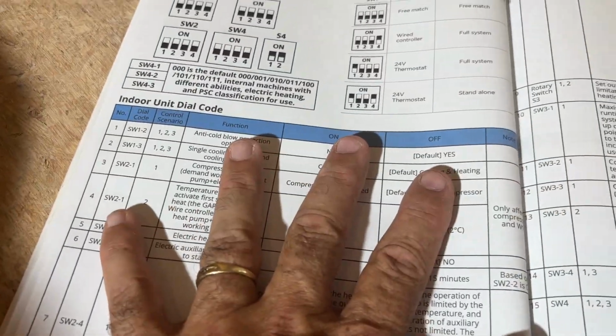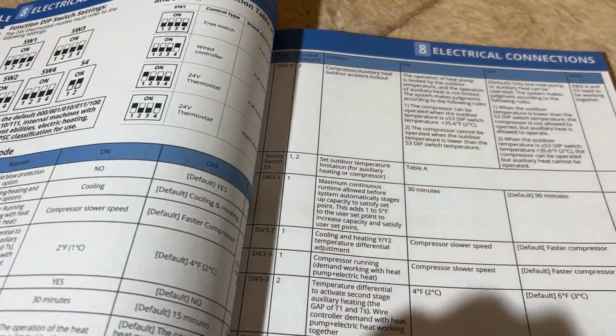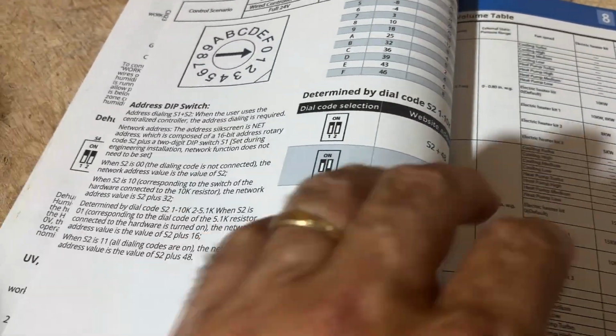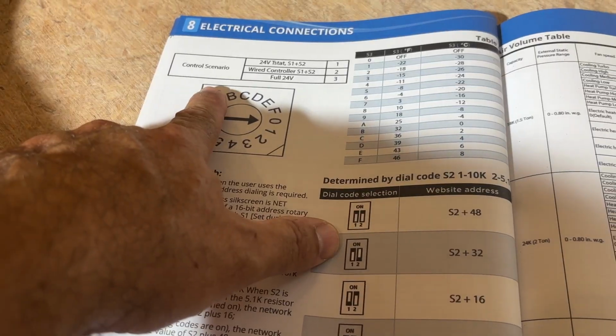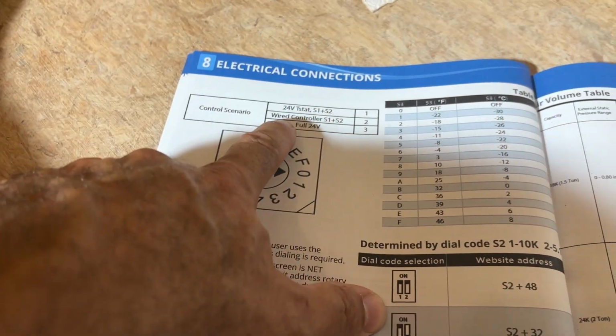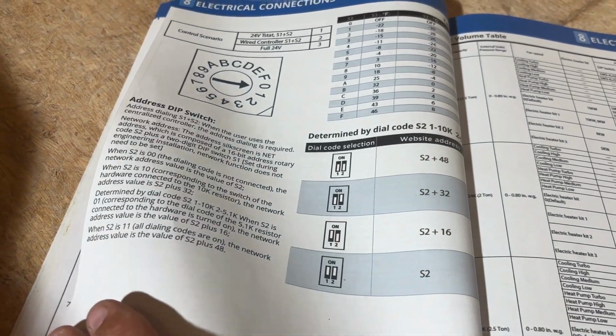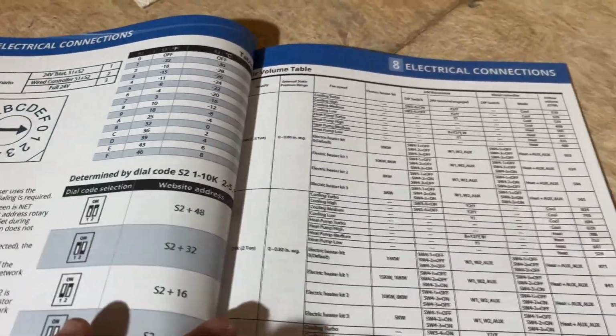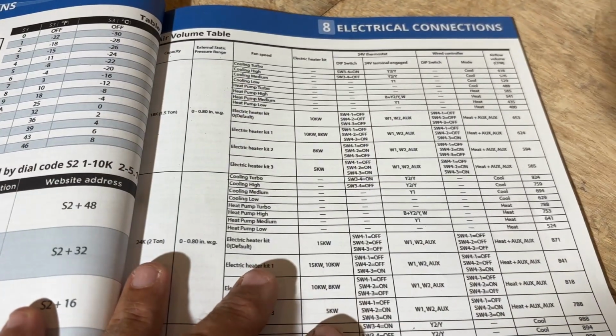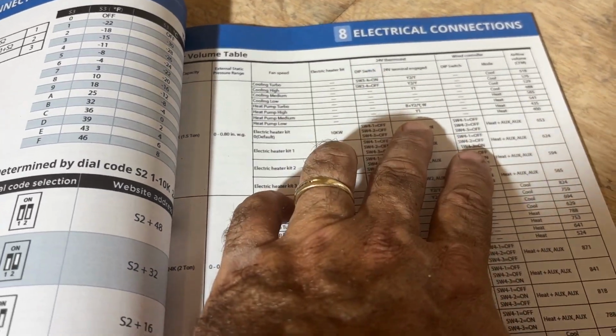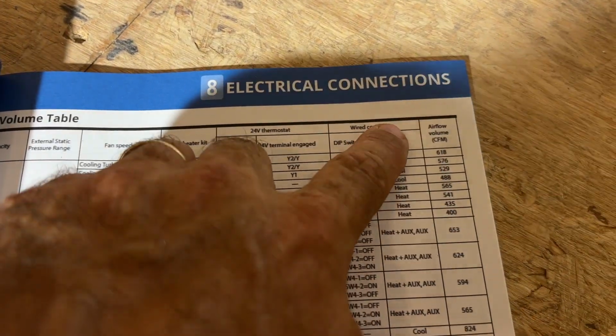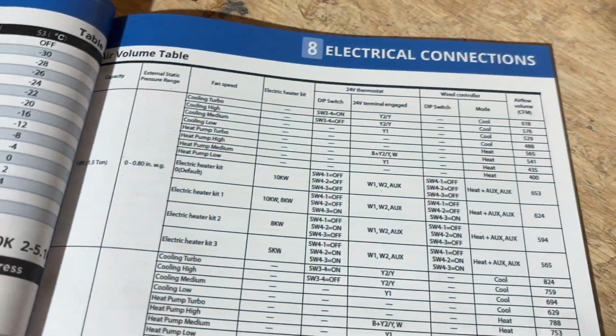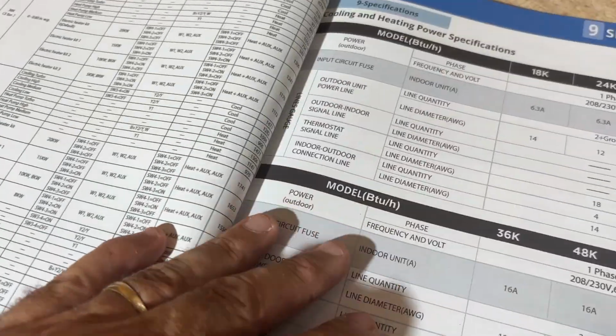We get into the dip switch settings, which we'll look at a few of those, and the charts for that. Control scenarios. So control scenario 1, 2, and 3, and then based on that, you can set up your dip switches based on your control scenario. And then you have your air volume tables, which we're not going to get into testing, but I'm going to have a guy come in later and we'll test out the CFMs and see how we're doing with our ductwork and getting everything plumbed in, power specs, and that's about it.